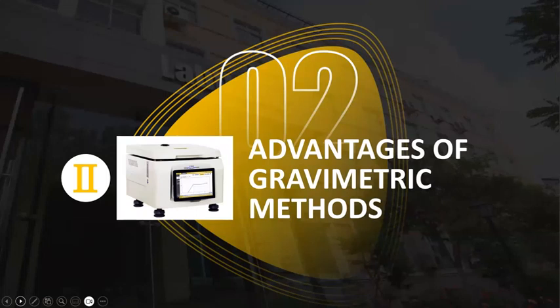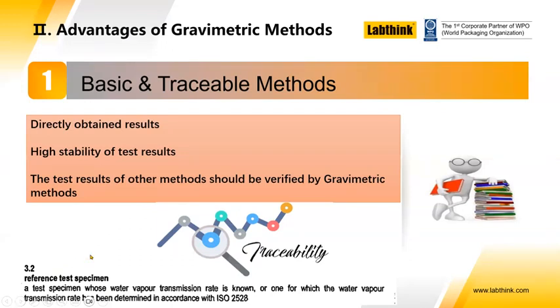So let's take a look at some of the advantages that gravimetric measurement can offer. One of the most important things about this method is the first point here. This is a directly obtained result. There is no sensor which is going to calculate light transmission through an infrared sensor or some kind of electrochemical reaction which is going to be converted into a measurement of the amount of water vapor molecules passing the center. This is a directly obtained measurement. So we're measuring directly weight gain or loss. So this is important. The high stability of the test results. If any of you have been familiar with ASTM E96, you'll know that when you do the test manually, it can take several days, and we are concerned with the measurement and changes in weight over a long period of time to get accurate and stable results.